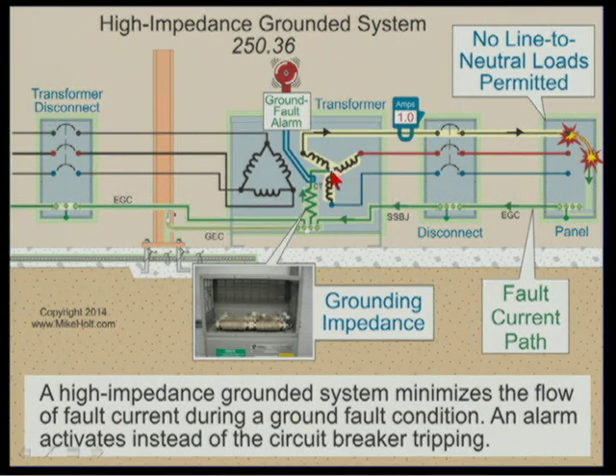This high-impedance grounded system means that you take the system itself, and you're actually putting a resistor in series. So this is no longer a solidly grounded system, but we're putting a resistor between the X0 and the case of that transformer, and then the case of the transformer is going to be grounded.